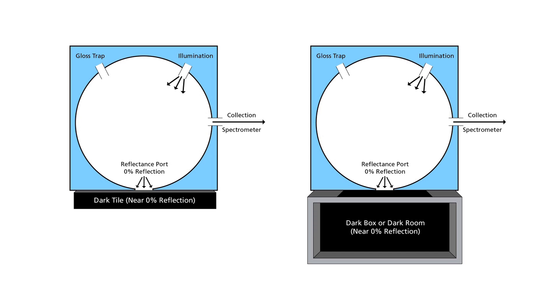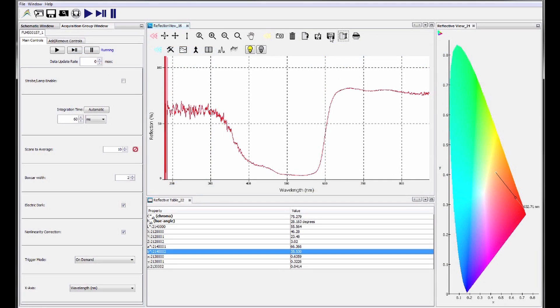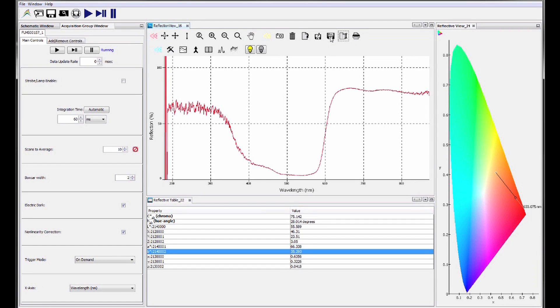With the light source on, either place a dark tile with very low reflectance over the port, or face the sphere's reflectance port into a dark box or dark room with no external light. This is very important to improve the accuracy of your measurement.